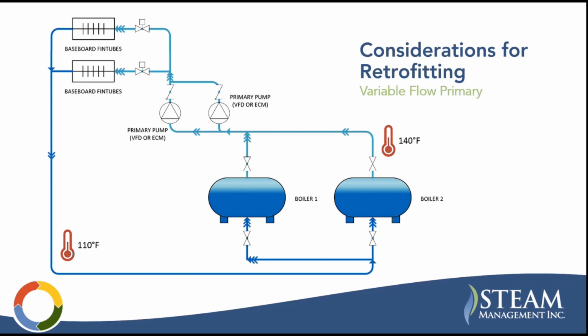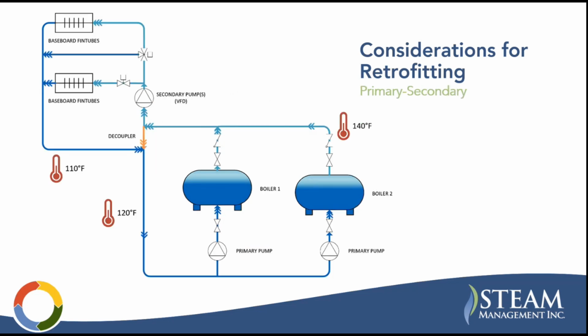I mentioned variable flow primary is going to be your recommended configuration by most manufacturers. Again, that is because you are going to get that minimum return temperature. This system is showing a condensing mode where you're able to turn that supply temperature down to 140 degrees and get a low return temperature to promote condensation of the flue gas in the boiler. Unfortunately, a lot of systems are already set up for primary-secondary, but those can be conducive to condensing boilers as well, and they certainly have their advantages.